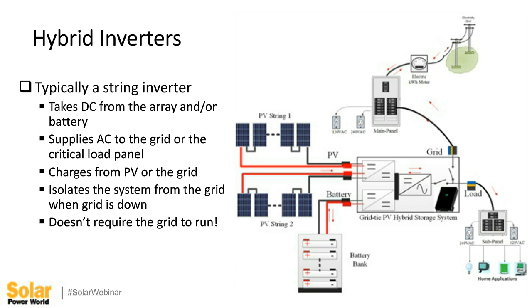It isolates the system from the grid when the grid goes down. As you well know from string inverters, when the grid goes down, you've got to isolate yourself so that you're not feeding power back. A hybrid inverter has kind of a unique situation here in that it's got to isolate itself from the grid, but still provide power for the critical load support.